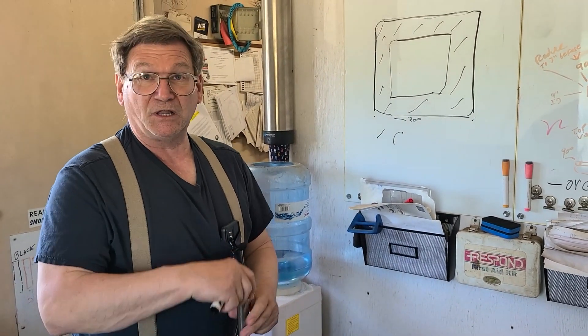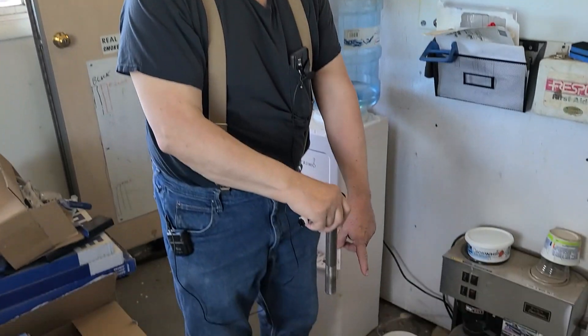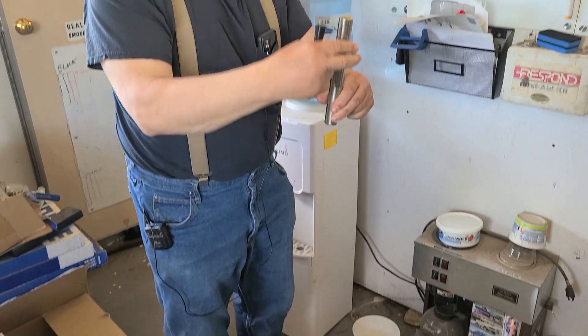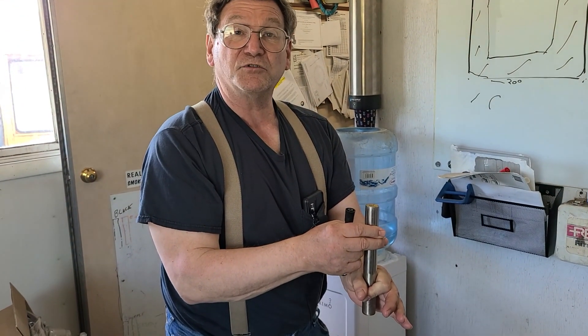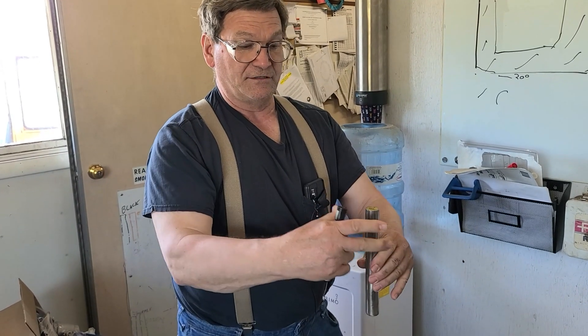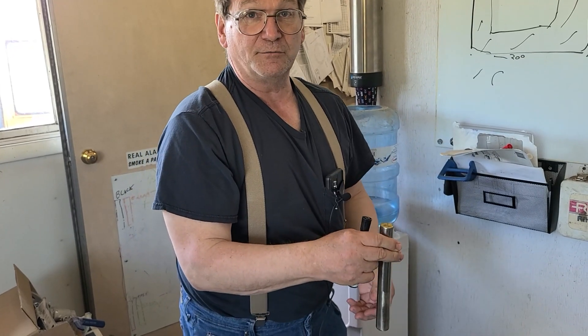You have pumps called a line shaft pump, where there's a whole bunch of shafts going together that go down into a well. The pump is way down at the bottom, and all of these pieces of shaft in between will have bushings. There's pipe on the outside, and because of the water flowing over this, it lubricates those bushings — they're just water-lubricated bushings.